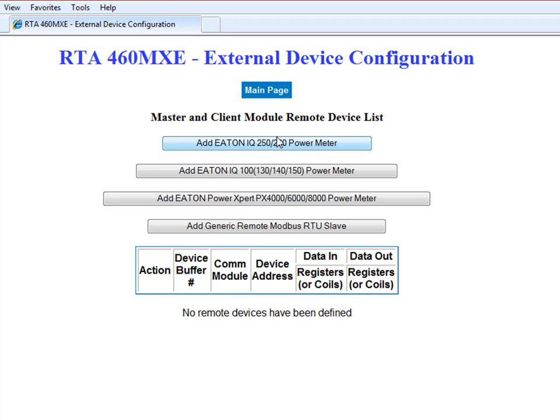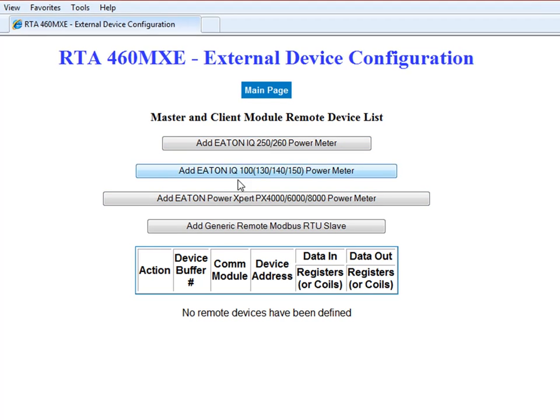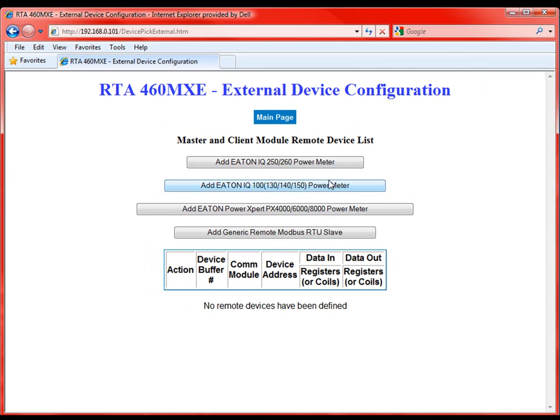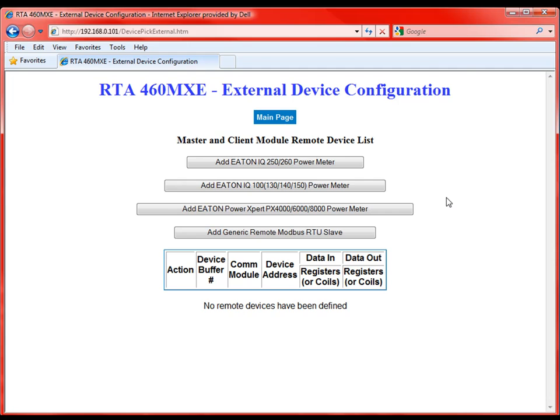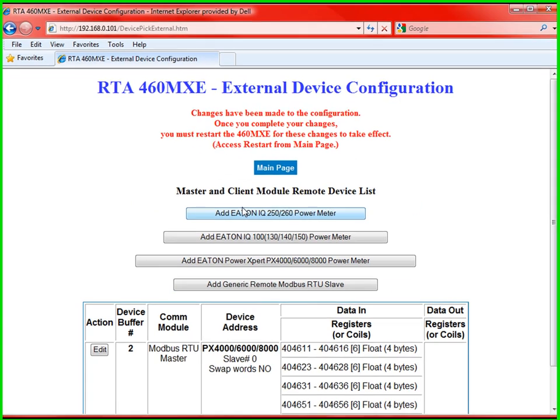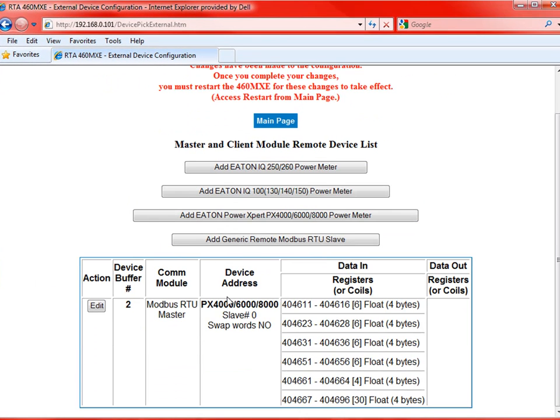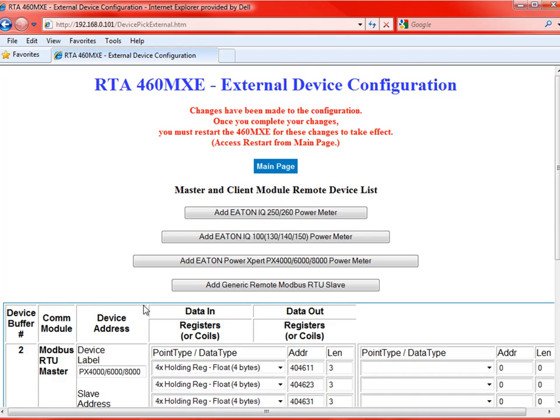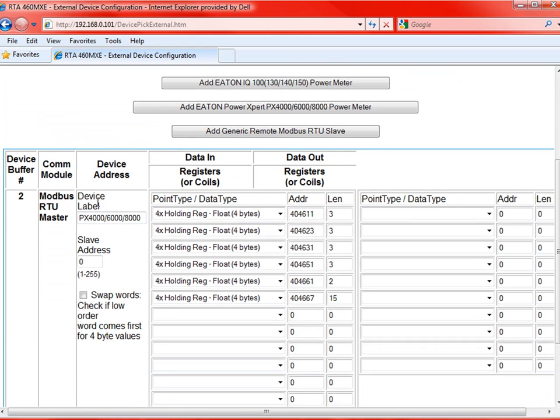So from here we can decide to add a power meter, whether it's a 250, 260, one of the IQ 100 level power meters, or one of the power expert meters. You can add any number or any combination of these power meters. You're also able to add generic Modbus RTU slaves in case there are a few that may be near this device that need to be accessed by BACnet. For the purpose of this video, we're going to skip the generic device. Let's just go ahead and add a power meter. So first off, let's add a power expert power meter. For simply adding that, you'll see that we have added a slave device for our Modbus master to pull.